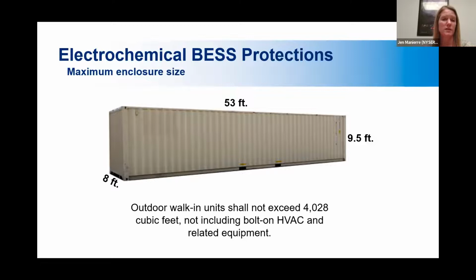There's also a maximum enclosure size. So outdoor systems throughout the code have slightly less strict requirements than systems that are located in buildings. So there's a maximum enclosure size that it can be and still be considered a quote unquote outdoor unit. If it gets any bigger than that maximum enclosure size, it's basically just going to be treated as a building in the fire code, and whatever indoor requirements are in there would apply. So this is just the largest an enclosure can be for an outdoor system before it starts to be considered an indoor system. It's basically the size of a shipping container, the volume of a shipping container anyway.